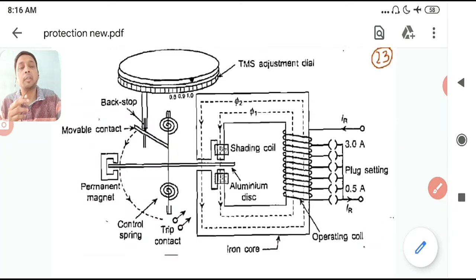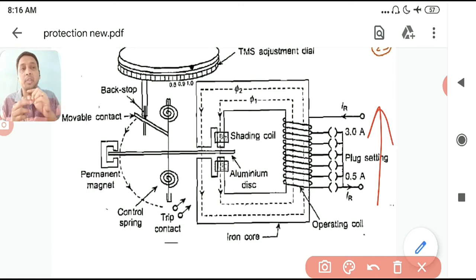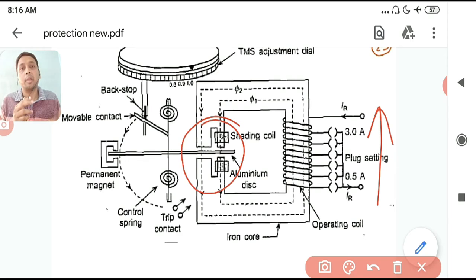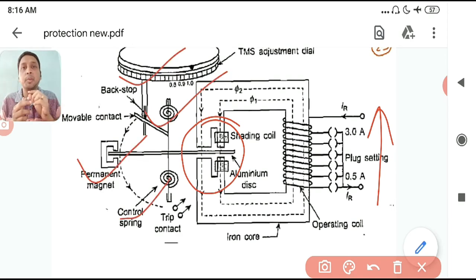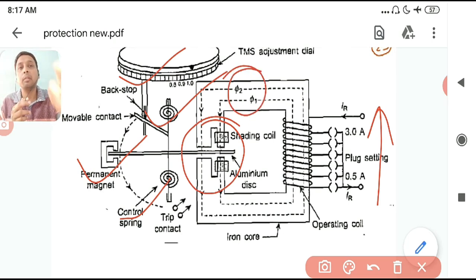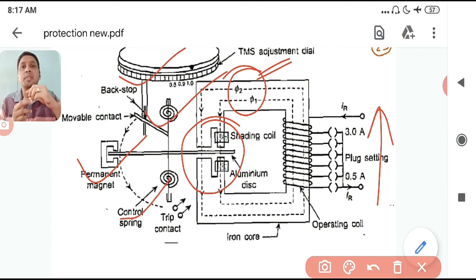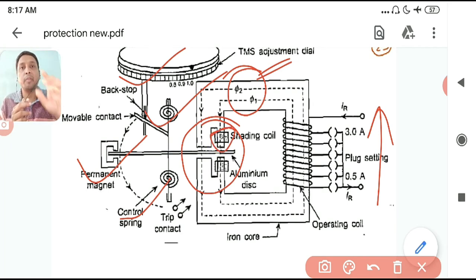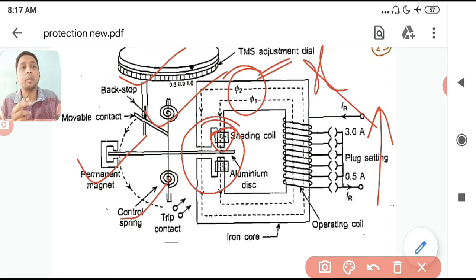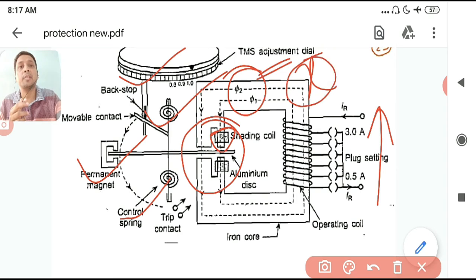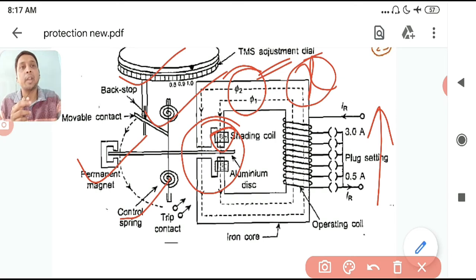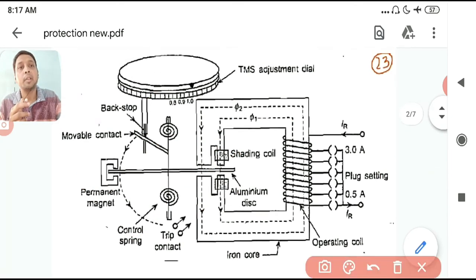Now, regarding why the plug settings go upward — with everything else fixed, the disc rotates when the flux exceeds a certain threshold value. That force depends on φ1 and φ2, with the angle between them fixed by the shading coil. So the threshold depends on φ1 and φ2, which let's call a value x. Anything above x makes the disc rotate.